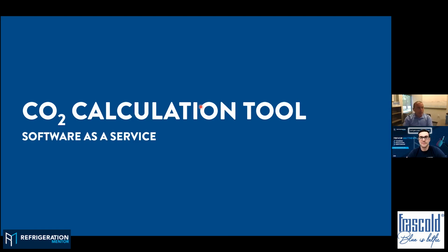Well, yeah, if you see on our selection software, this is our standard superheat we put for both transcritical and subcritical compressors. There is a lot of talking as usual on superheat and even more now on CO2, because we all know how the solubility of the oil is affected by CO2. It's clear that the POE oil can be diluted by CO2 by far more than other refrigerants and oil. Therefore, it's always important to guarantee at least a minimum superheat.